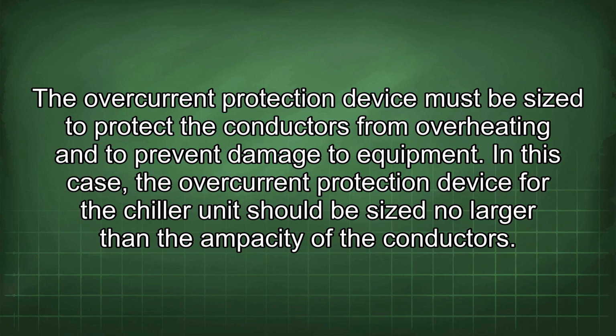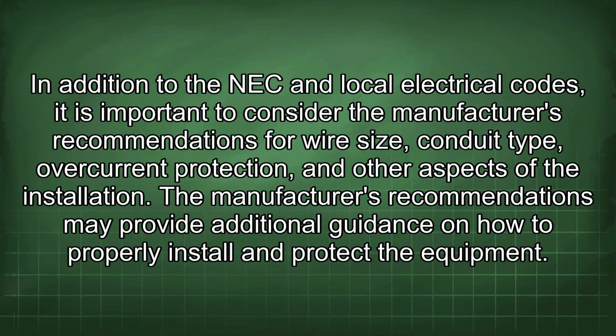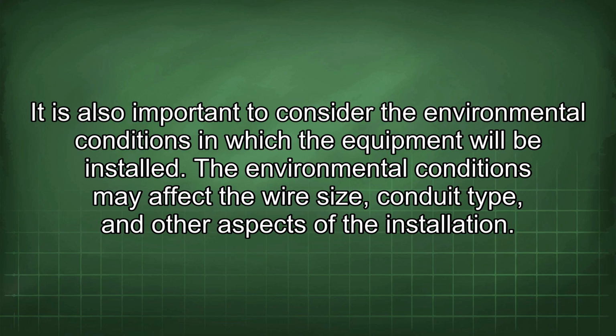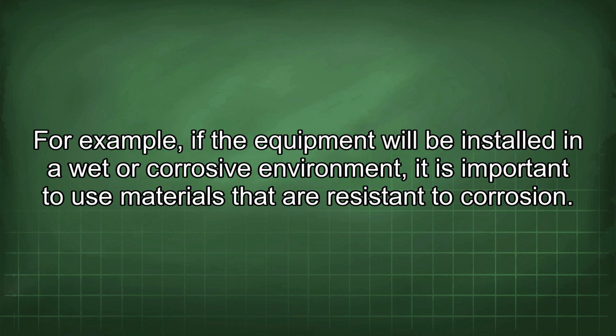In addition to the NEC and local electrical codes, it is important to consider the manufacturer's recommendations for wire size, conduit type, overcurrent protection, and other aspects of the installation. The manufacturer's recommendations may provide additional guidance on how to properly install and protect the equipment. It is also important to consider the environmental conditions in which the equipment will be installed. The environmental conditions may affect the wire size, conduit type, and other aspects of the installation. For example, if the equipment will be installed in a wet or corrosive environment, it is important to use materials that are resistant to corrosion.